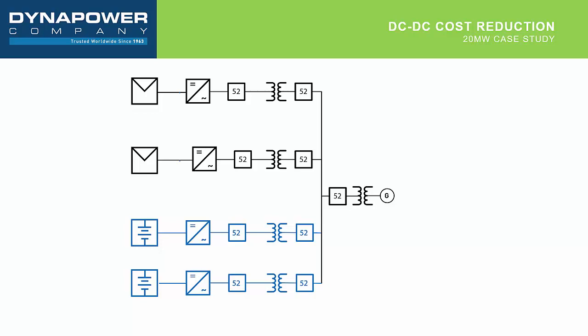So let's consider, just to make the numbers round, a basic 20 megawatt case study where we have a 20 megawatt solar array coupled with 20 megawatts of storage. So in the AC coupled system, you have here in blue down below your AC coupled inverter, as well as the switchgear, the step-up transformer, and the AC collection system, all tied together on the medium voltage bus with the PV array. And this would be considered a very standard AC coupled configuration.